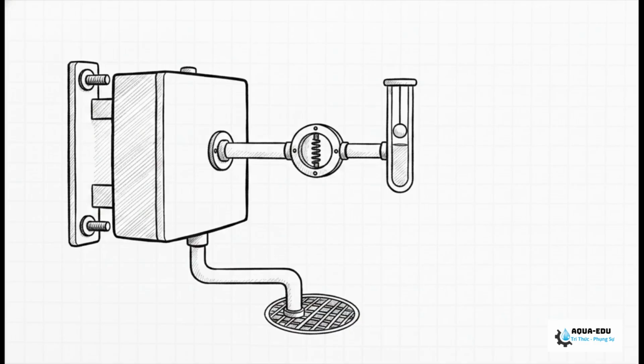You'll want to dial in a nice steady flow reading, somewhere between 100 and 300 milliliters per minute on your rotameter. Finally, route your gray waste line directly into a safe chemical drain. No floor leaks allowed on our watch.